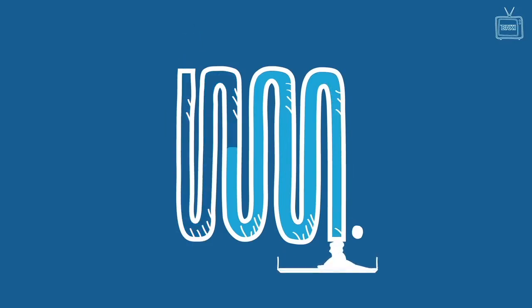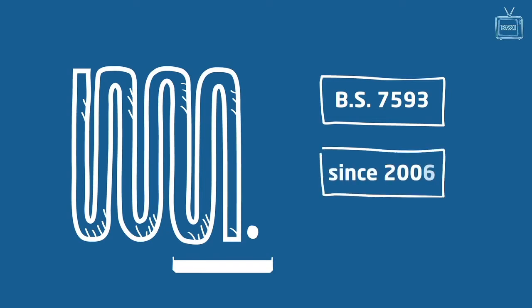Baxi recommends you thoroughly flush the system according to the guidance given in British Standards 7593, the code of practice for treatment of water in domestic hot water central heating systems. This has been a requirement of the building regulations since 2006.